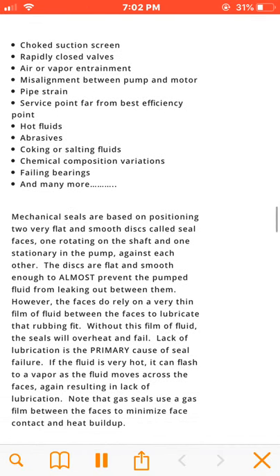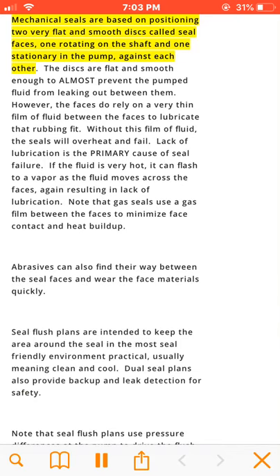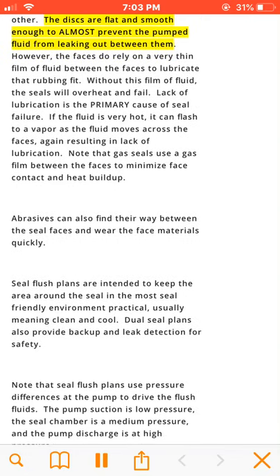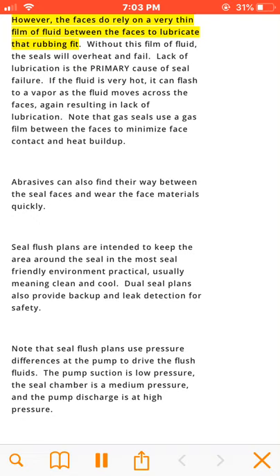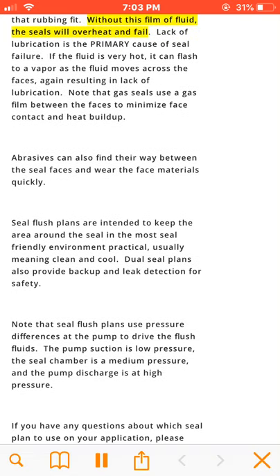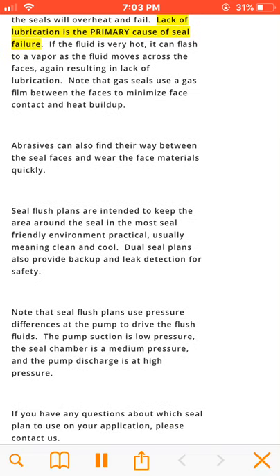Mechanical seals are based on positioning two very flat and smooth discs, called seal faces — one rotating on the shaft and one stationary in the pump — against each other. The discs are flat and smooth enough to almost prevent the pumped fluid from leaking out between them. However, the faces do rely on a very thin film of fluid between them to lubricate the rubbing fit. Without this film of fluid, the seals will overheat and fail. Lack of lubrication is the primary cause of seal failure; if the fluid is very hot, it can flash.